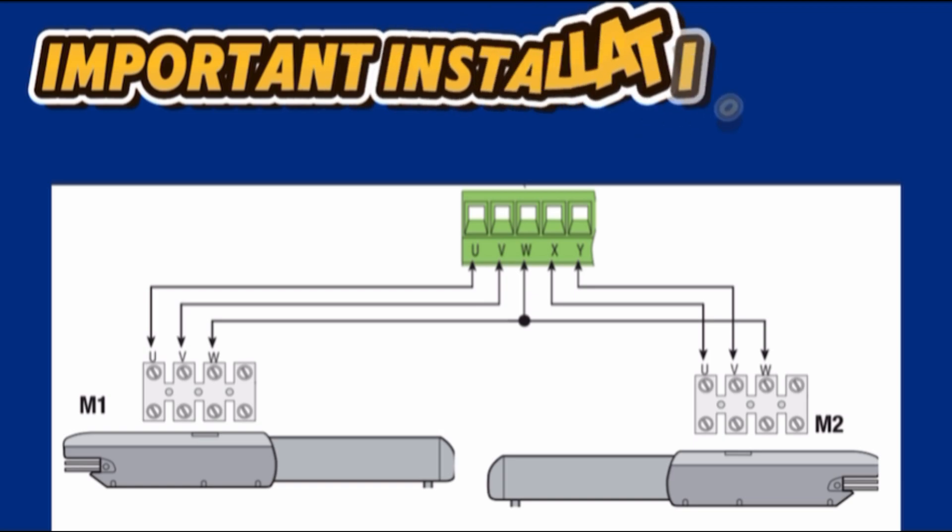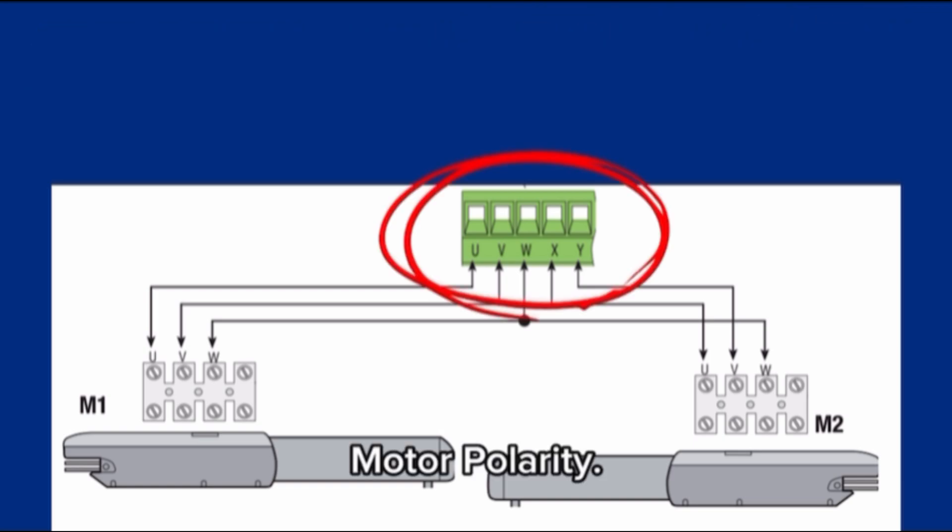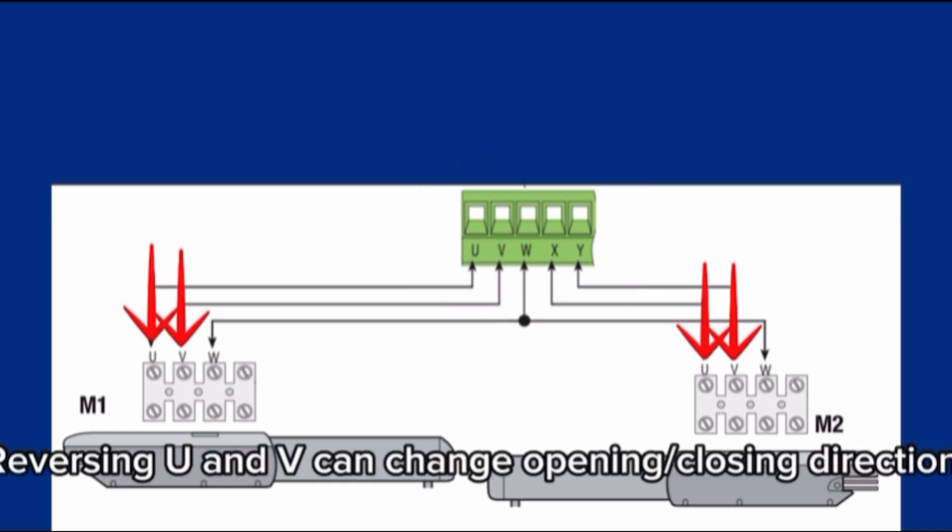Important installation tips. Motor polarity. Double check the terminals of UVW orientation for correct rotation. Reversing U and V can change opening closing direction.